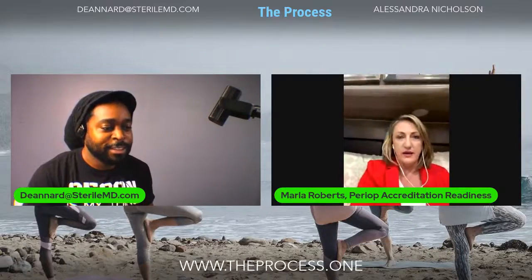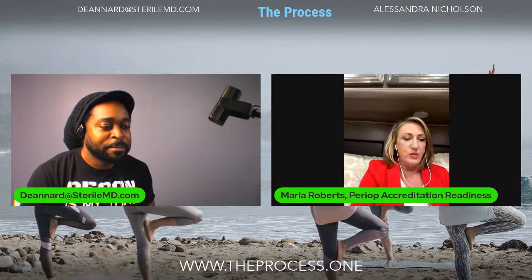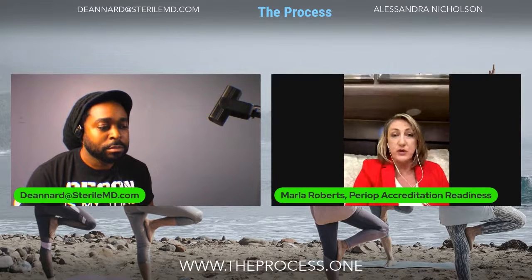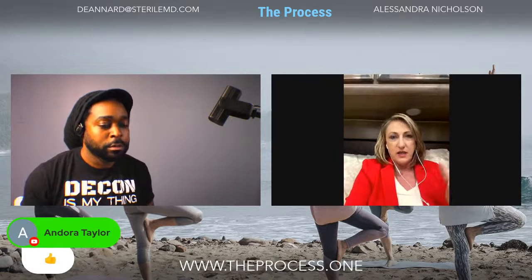Yeah, I think environment of care and infection control. So poor lighting in there, the lack of terminal cleaning or documenting that any terminal cleaning is going on. I went into one place and literally I didn't have to ask if they were terminally cleaning. There was so much dust on the wall, I could write my name on it. And this was in the prep and pack side.